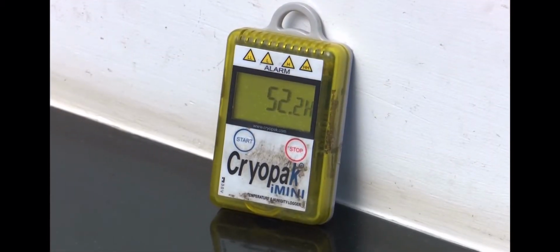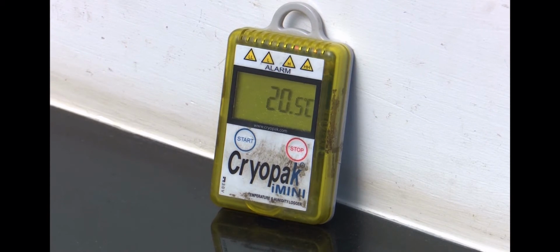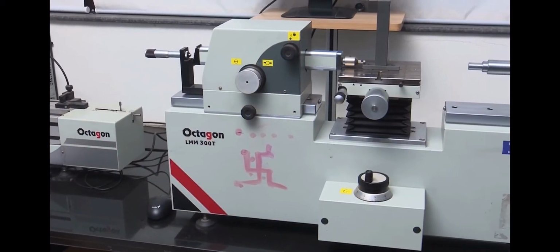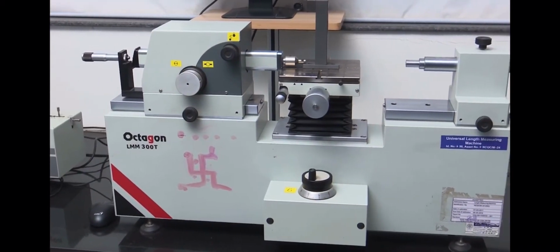Before starting calibration, ensure that environment condition is maintained. The temperature should be between 20 ± 2 degrees centigrade and humidity should be 40 to 60% RH. For calibration, we will use length measuring machine as reference standard.